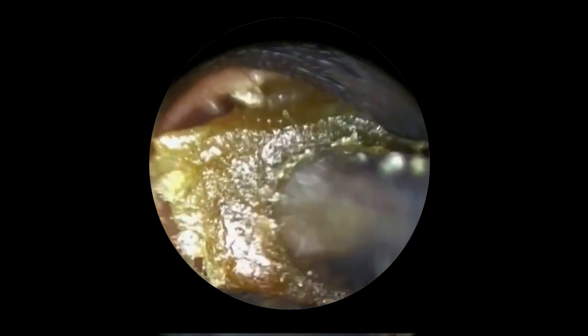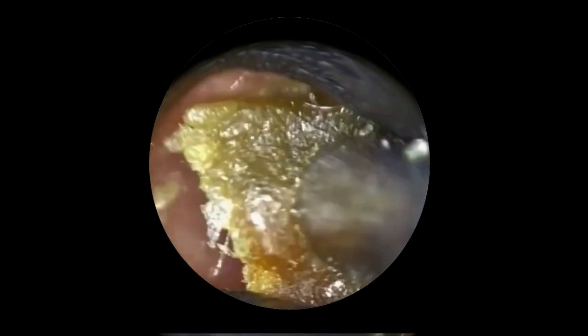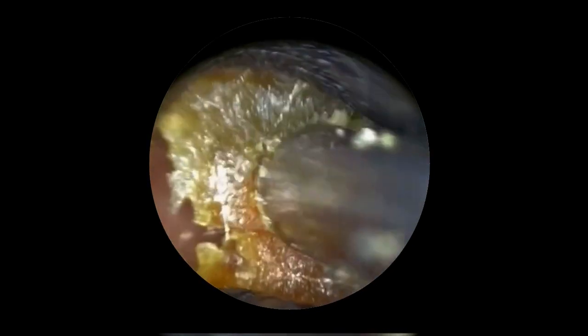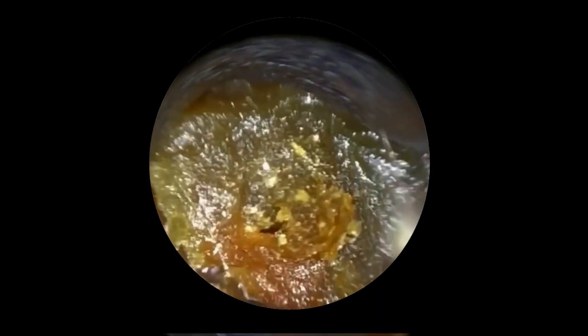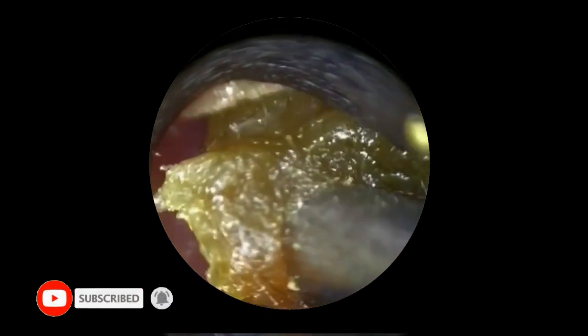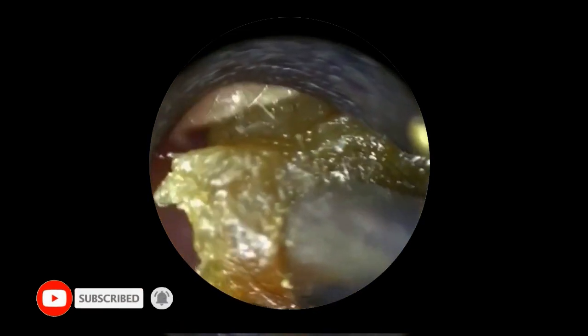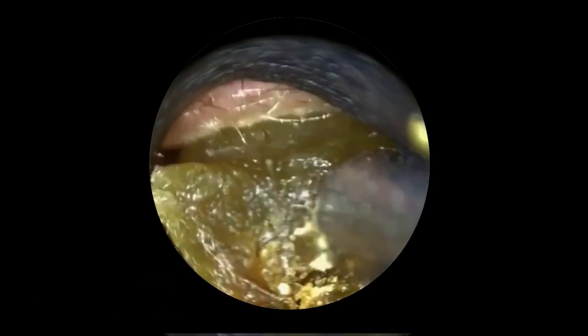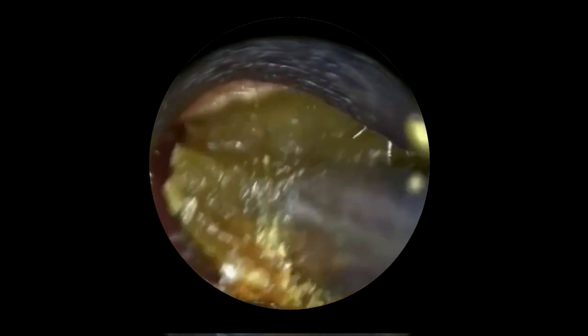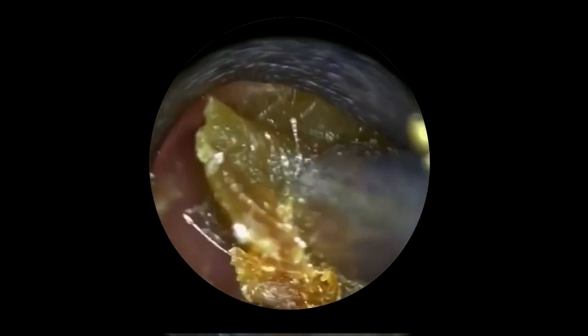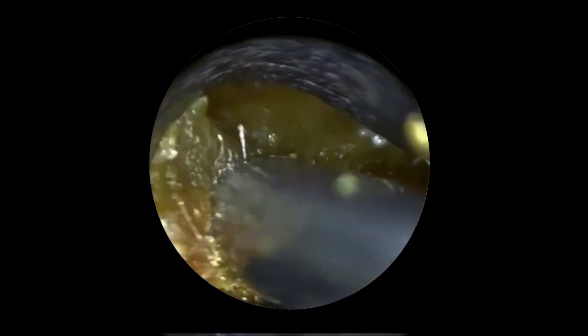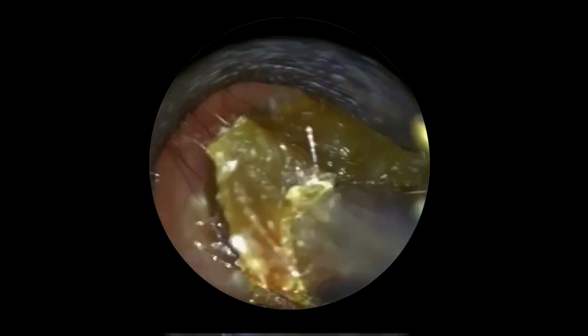And because of the fact that we're using this unique speculum designed by Clearwax, which we've applied for a UK patent, this device is actually a class 1 medical device. It doesn't need a class 2 certification. So class 2 certification is when, in the case of an endoscope, if there's a lumen there, so a cavity where you have to insert an instrument through, and that lumen to that cavity is not disposable and it's being reused, there has to be proper sterilisation methods being used to do that. So with the wax scope, we mitigate that because of the disposable speculum.